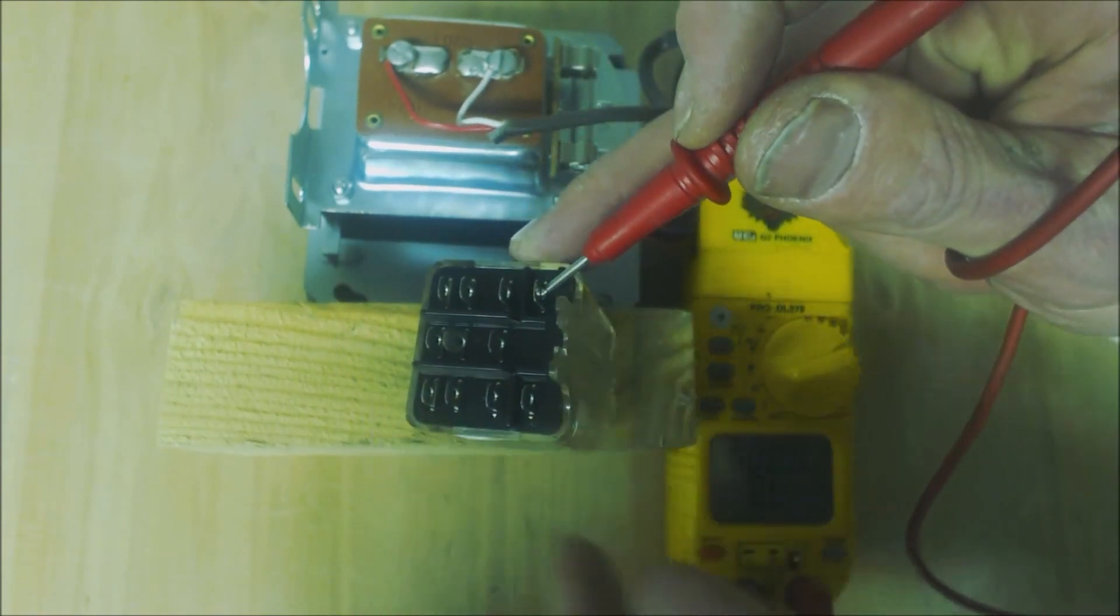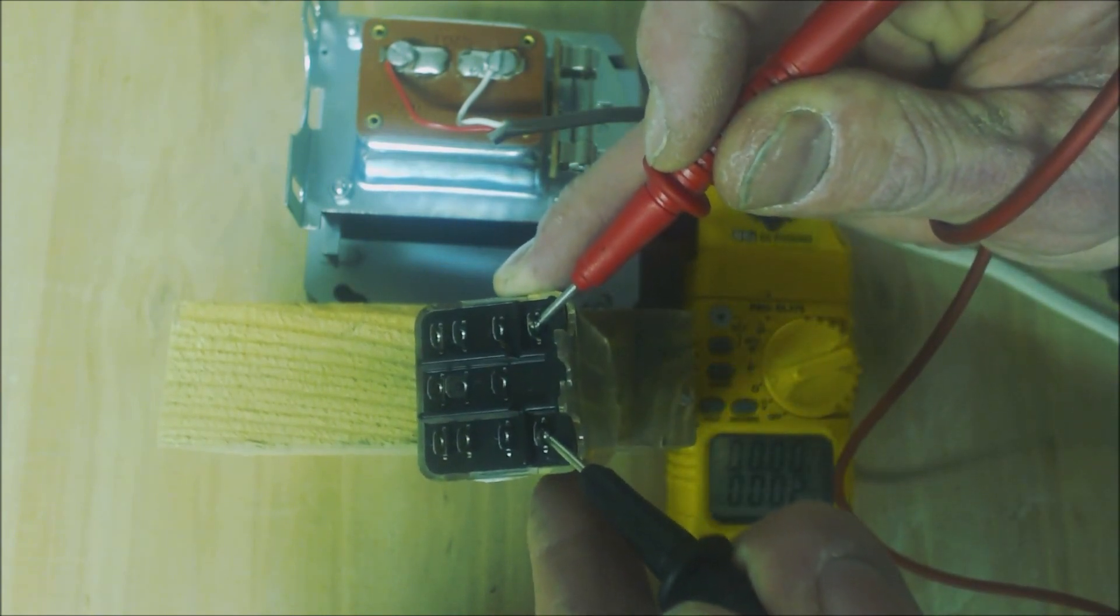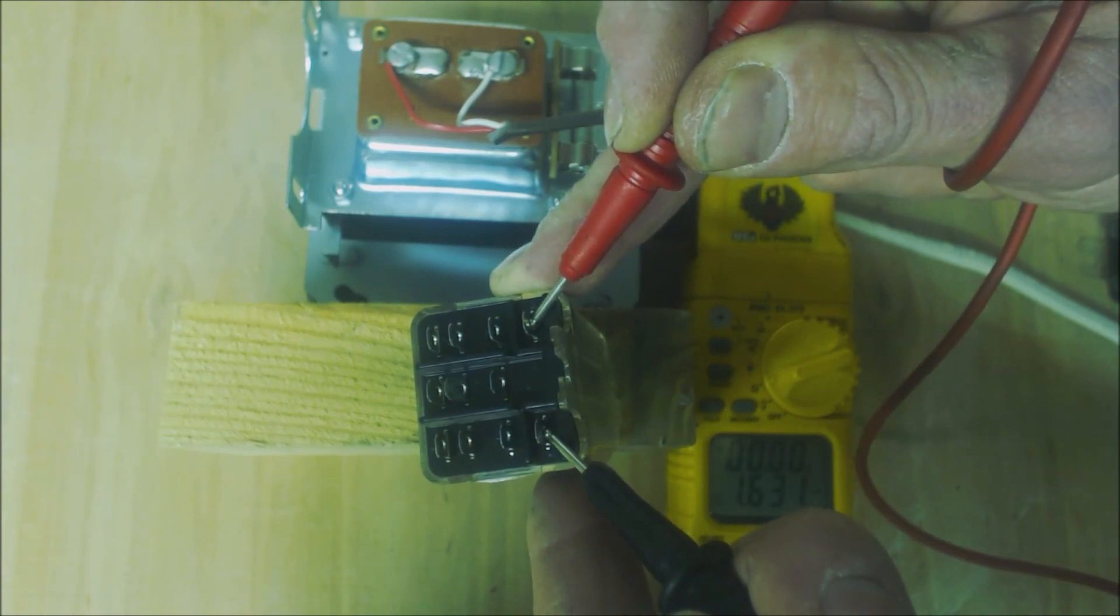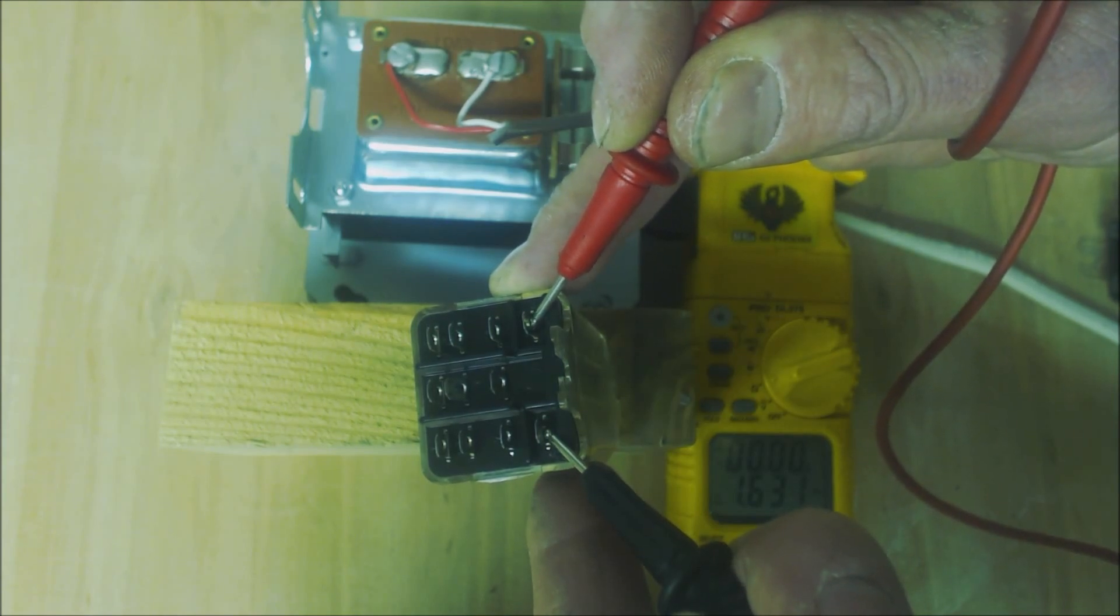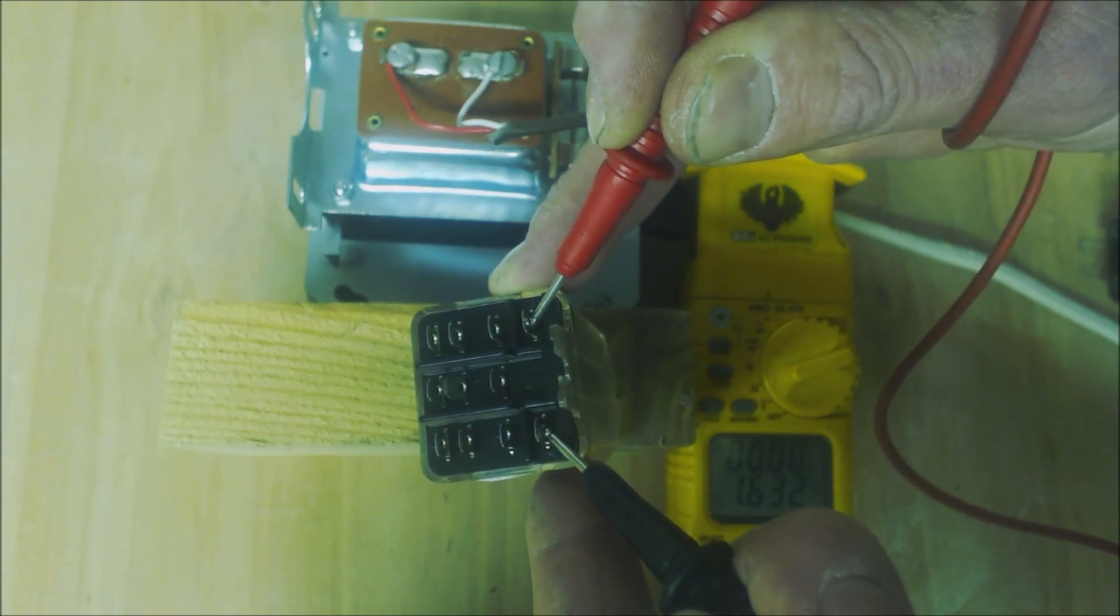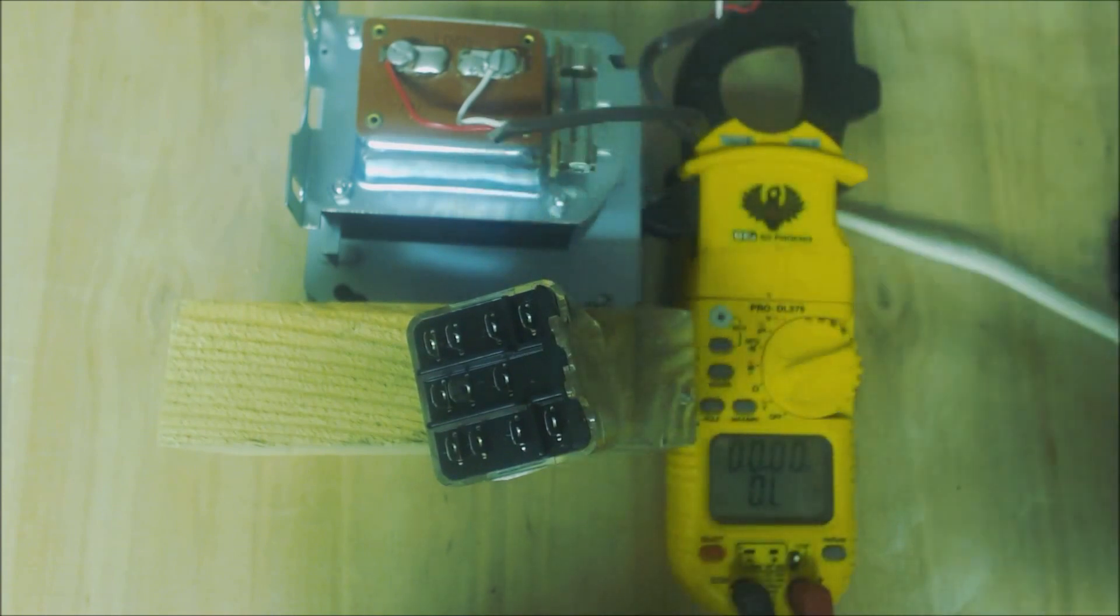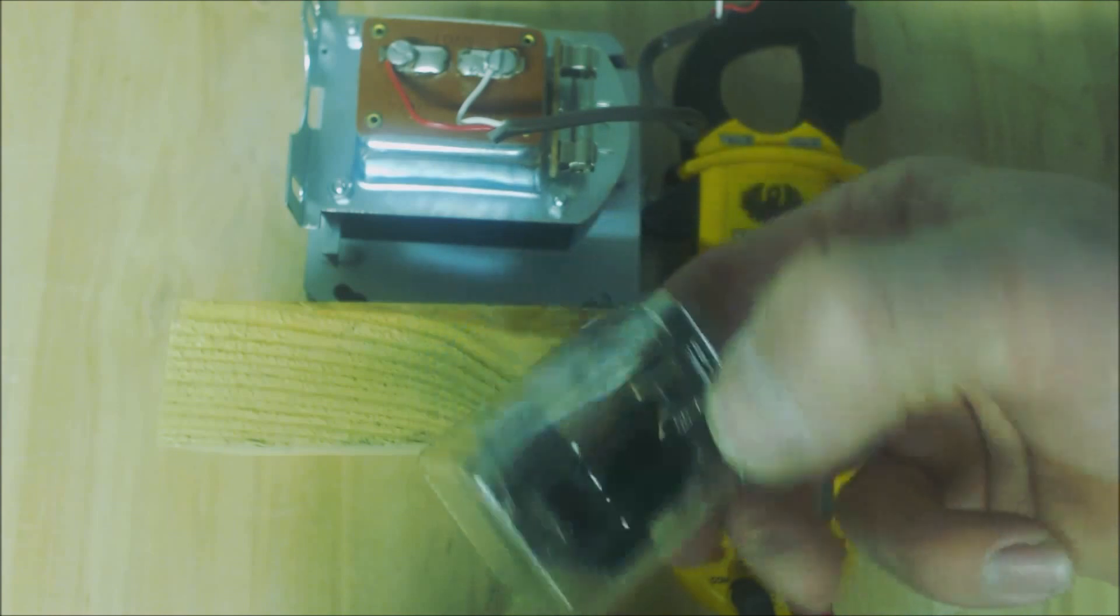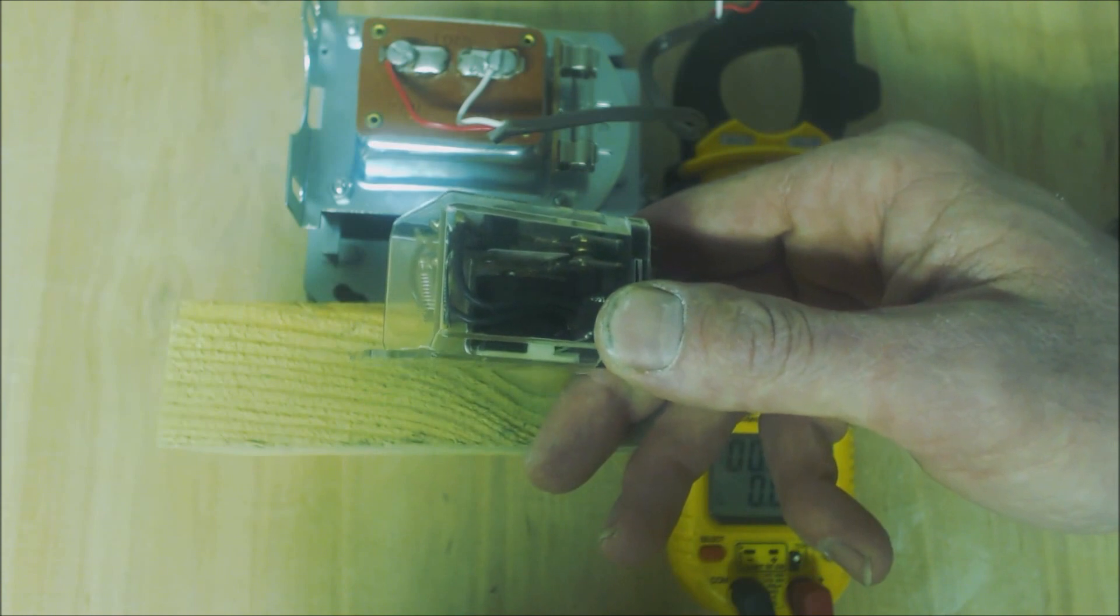Here's the 120 volt one, and we're going to test the coil. Remember the coil is closest to the mounting bracket, so it's going to be closest to where you're mounting it to the side of the furnace or the air handler. This one is 1.63 kilo ohms, so that's 1,632 ohms of resistance. It's a lot higher resistance since it's being powered with 120 volts.